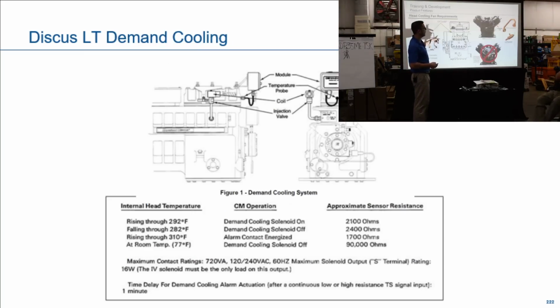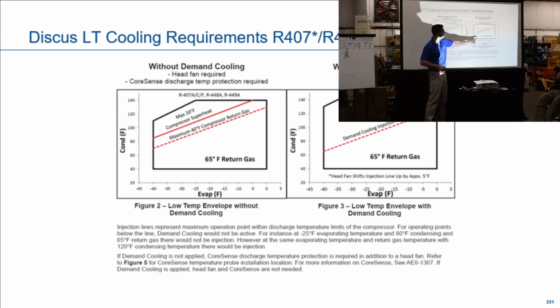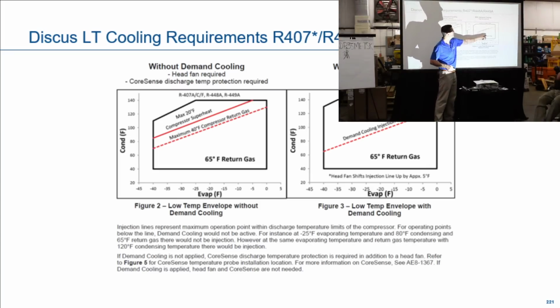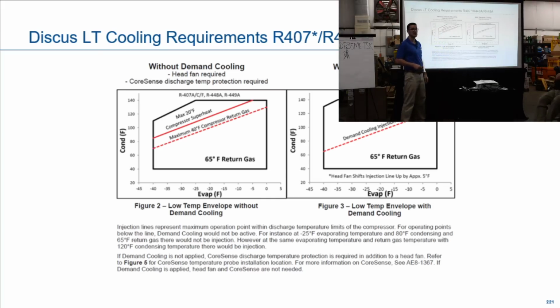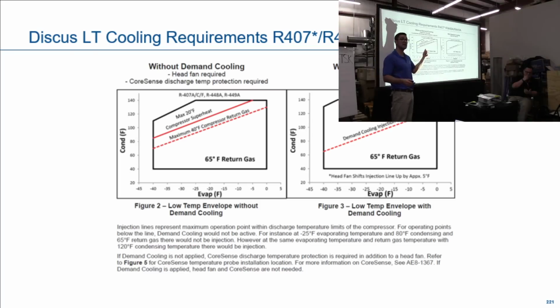So this is 407, 448 now. This was 404. So now, if I'm right here in the operation envelopes, head cooling fan optional with demand cooling. So you need demand cooling on this compressor. When you get above this line here, demand cooling is going to inject. So now if you're doing a retrofit from 404 to a new refrigerant like 448, 449, you might have to start adding demand cooling on those compressors.